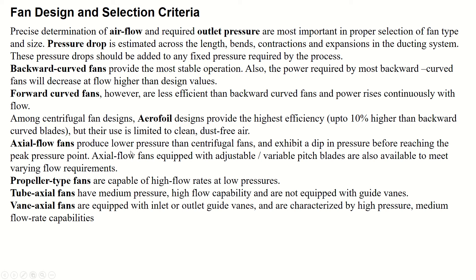Axial flow fans produce lower pressure than centrifugal fans and exhibit a dip in pressure before reaching the peak pressure point. They are available with adjustable variable-pitch blades to meet varying flow requirements. Propeller-type fans are capable of high flow rates at low pressures. Tube axial fans have medium pressure and high flow capability without guide vanes. Vane axial fans are equipped with inlet or outlet guide vanes and are characterized by high pressure and medium flow rate capabilities.